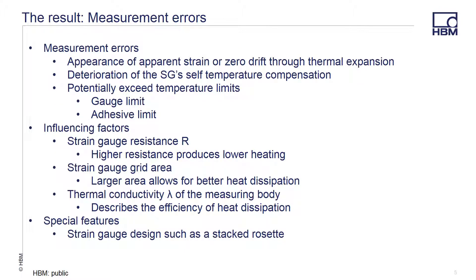Excessive heat in the gauge can manifest itself with a zero drift on the gauge. If the amount of heat generated is excessive, the gauge could run into self-compensation issues and perhaps cause other issues such as exceeding the adhesive temperature limit. To limit this, you can choose a higher resistance gauge as higher resistance produces lower heat. You can increase the physical size of the grid as the larger area allows for better heat dissipation. You can also change the measuring body to a material with better thermal conductivity, though that obviously isn't possible in most cases. You can also avoid some issues by not using special gauges like stacked rosettes, which have more difficulty in dissipating heat.